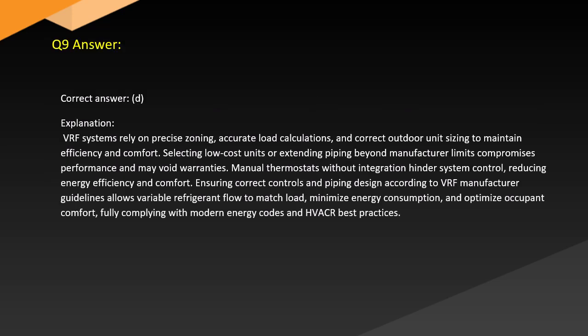Answer. Correct answer: D. Explanation. VRF systems rely on precise zoning, accurate load calculations, and correct outdoor unit sizing to maintain efficiency and comfort. Selecting low-cost units or extending piping beyond manufacturer limits compromises performance and may void warranties. Manual thermostats without integration hinder system control, reducing energy efficiency and comfort.